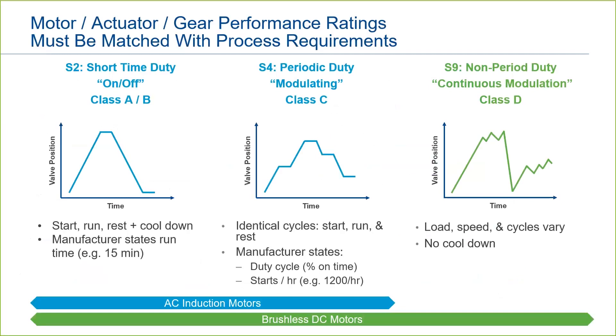Typically, we see S2 on-off and S4 modulating duty covered by AC induction motors. DC brushless motors can modulate continuously, but can also handle the less challenging S4 and S2 duties as well. The level of technology and robustness increases as we go from S2 to S4 to S9 service. S4 duty typically goes up to 1,200 starts per hour — that equates to a start every three seconds, which is pretty frequent and can cover a lot of applications. S9 is there really for control applications where continuous adjustment is the norm.